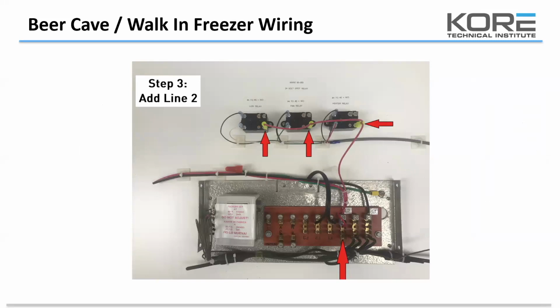The next step that we take at this point is we wire in the 208 power. Now this is the wiring for the beer cave and the kitchen freezers. We bring in the power from the condenser. We take it off the time clock and then move the wires down to the line side of the contactor, bringing the 208 volts down, and we attach that on the terminals that are labeled H1 from the factory. You'll see that I put L1 and L2 there.